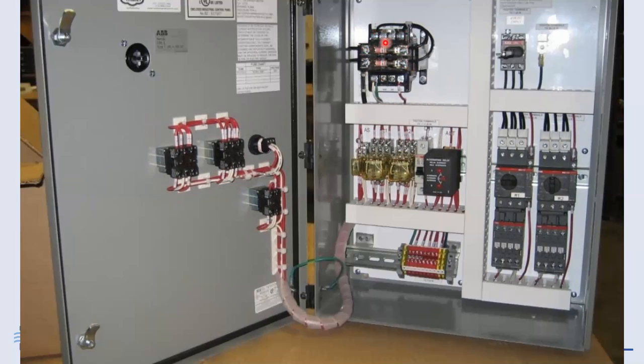Many times these pumps are operating on high voltages, 480 volts or more. But our control system, we don't want 480 volts, we want 110 volts. Something smaller that's a little bit safer for humans to interact with. So this transformer is going to take the high voltage and step it down to the control system voltage.